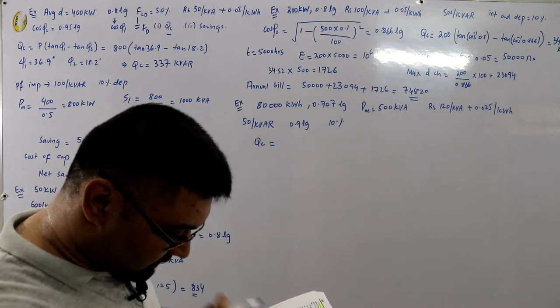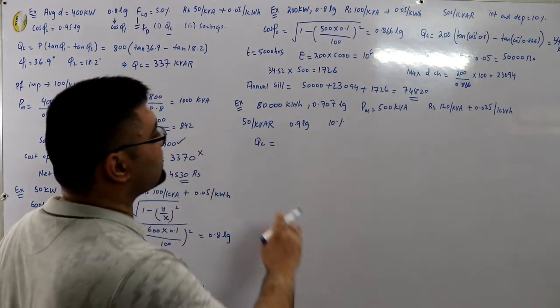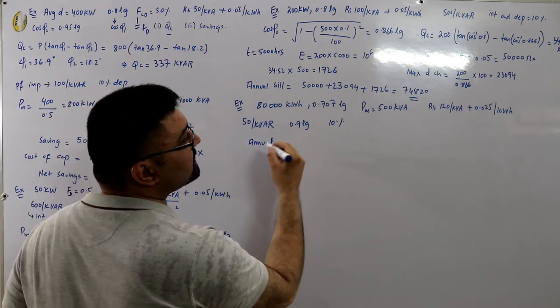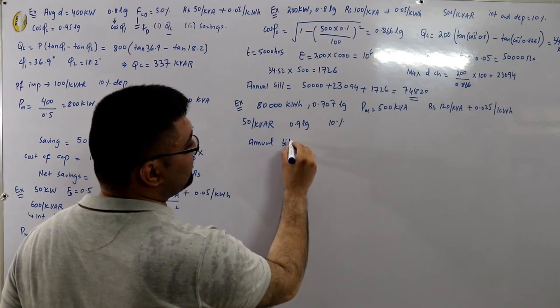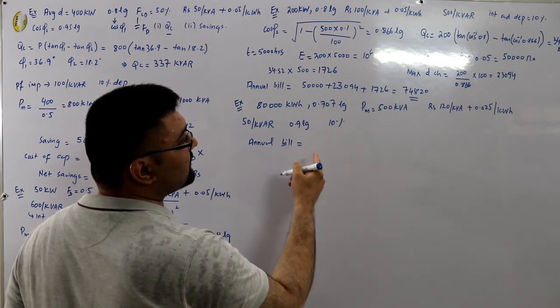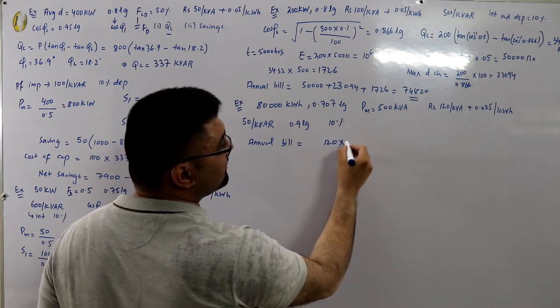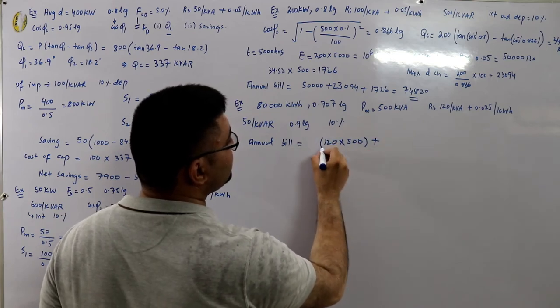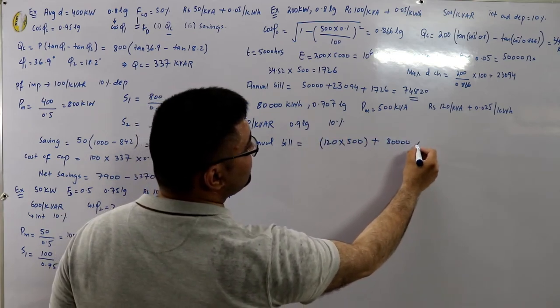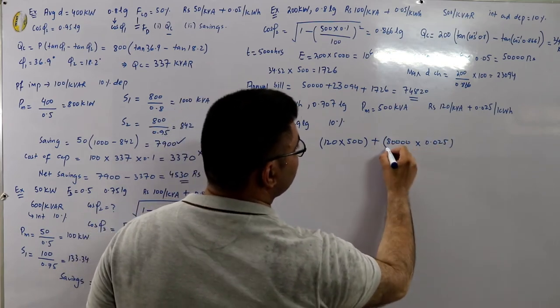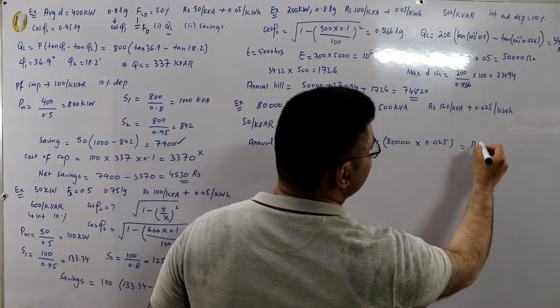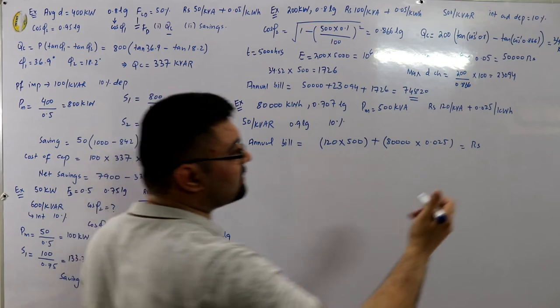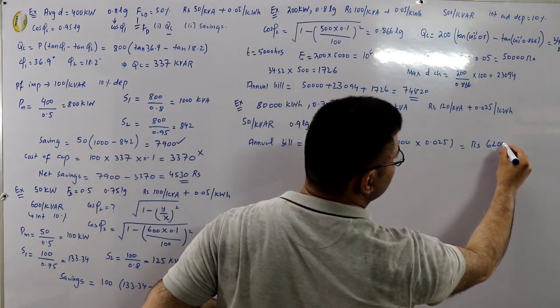Calculate the annual cost of supply before power factor correction. Annual bill = fixed cost + variable cost = (120 × 500) + (80,000 × 0.025) = 60,000 + 2,000 = approximately 62,000 rupees.